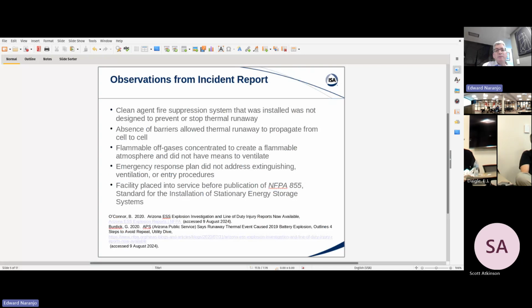The second issue is the absence of any barriers to prevent thermal runaway. When you have cells that can be isolated and compartmentalized, you can reduce the scale of an incident by ensuring one single cell burns without affecting the others. In this case, there was no such thing, no passive barriers to protect other cells against the failure of one cell.